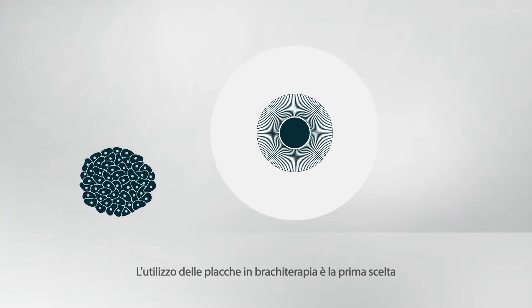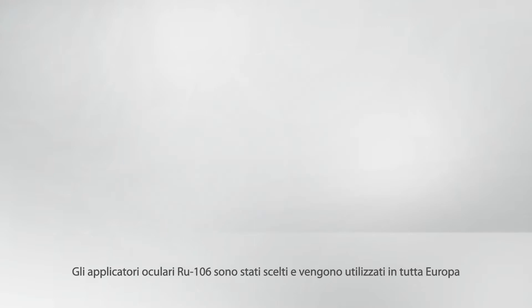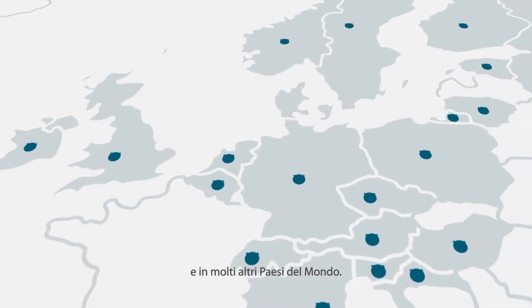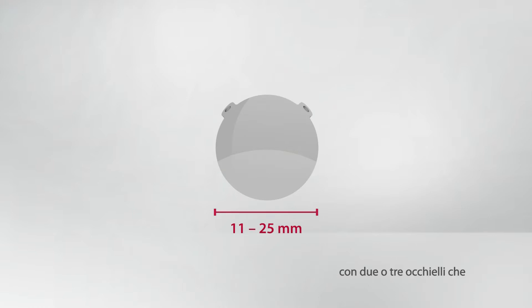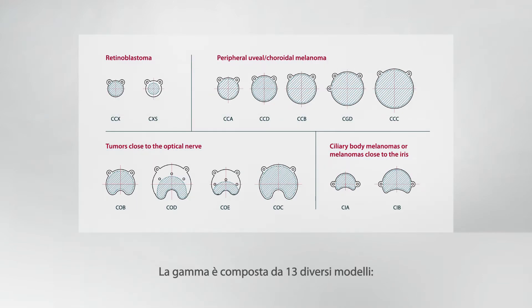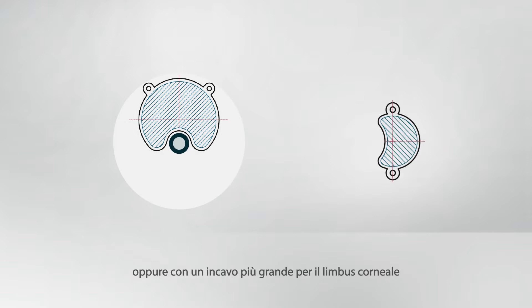Plaque Brachytherapy is the first choice when it comes to uveal melanoma treatment. Ruthenium 106 eye applicators are chosen and used across Europe and several other countries around the world. The applicator is a concave plaque with a diameter of 11 to 25 millimeters and has two or three eyelets that are sutured to the sclera. The product range consists of 13 different types with a narrow notch for tumors close to the optic nerve, a wide notch for the corneal limbus, or without notch.